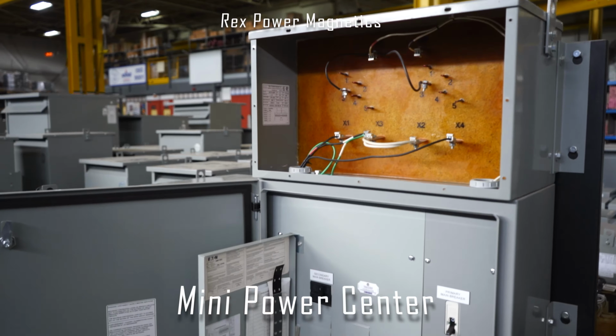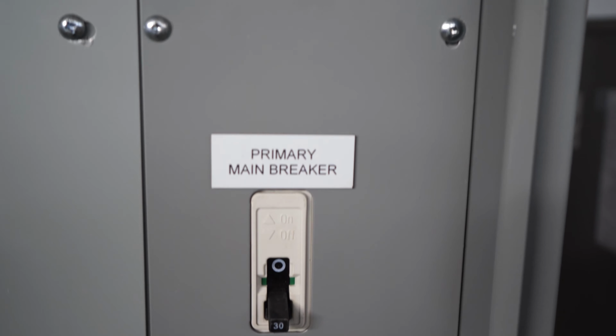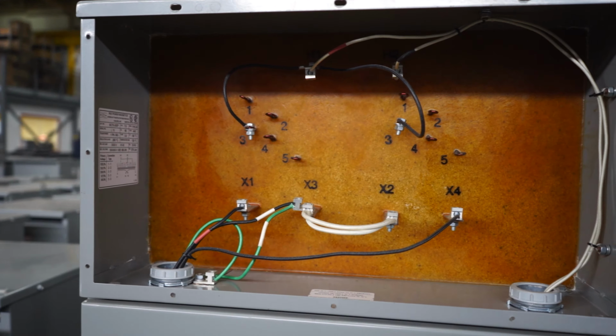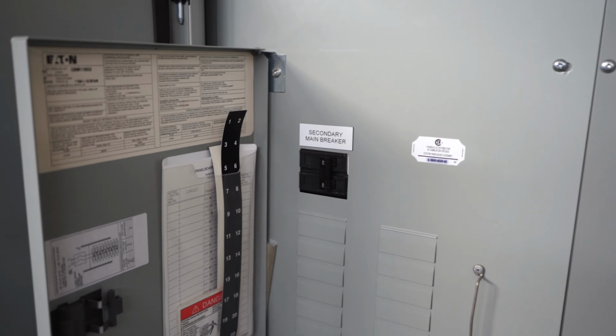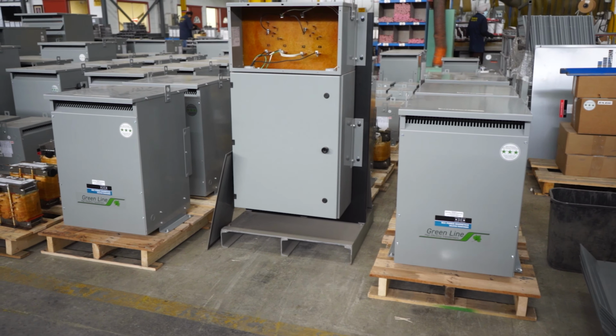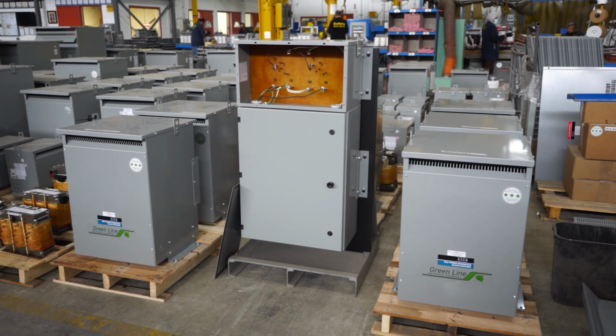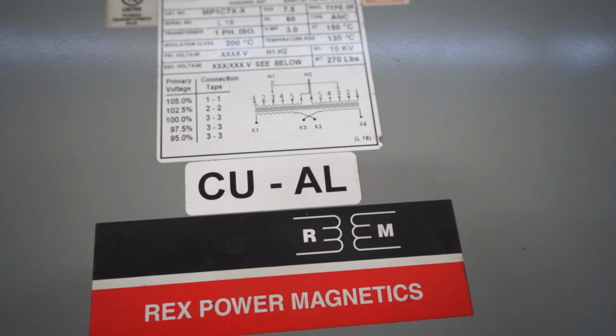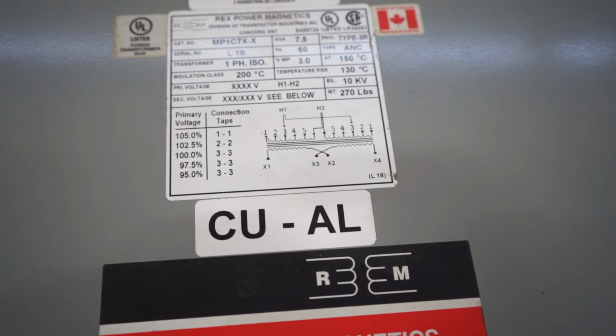Rex Power Magnetics mini power centers combine a primary main breaker, an encapsulated dry-type transformer, and a secondary main breaker type distribution load center into a single enclosure, used where there is a 480 volt or 600 volt distribution system and loads requiring 120 to 240 volt single phase or 208Y/120 volt three phase.